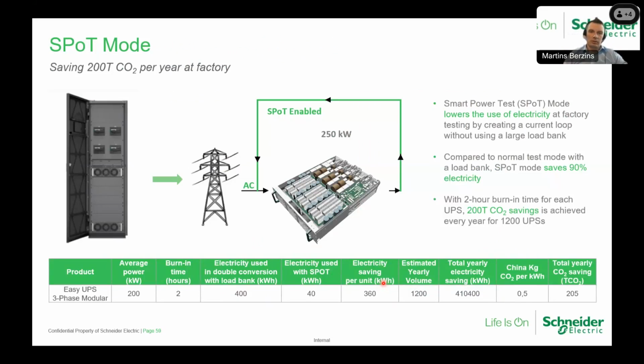by not using the load banks. So compared to normal test mode with a load bank, with the spot mode, we can save 90% more electricity. Here at the bottom we have a nice example. For example, if the average power of the UPS is 200 kilowatts and the load test or burn-in time is 2 hours, using the load bank you would consume 400 kilowatt hours of electricity. With the spot mode, it's only 10% of that. So basically, in spot mode, it consumes only 40 kilowatt hours. So it's a 360 kilowatt hours savings per UPS.